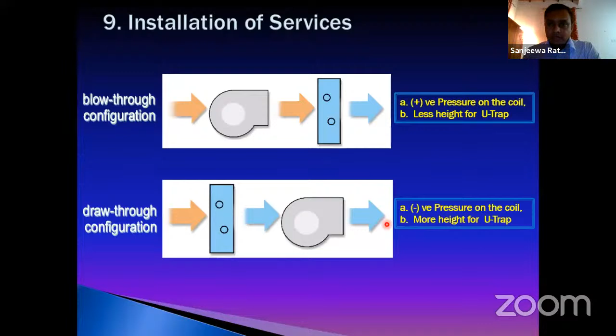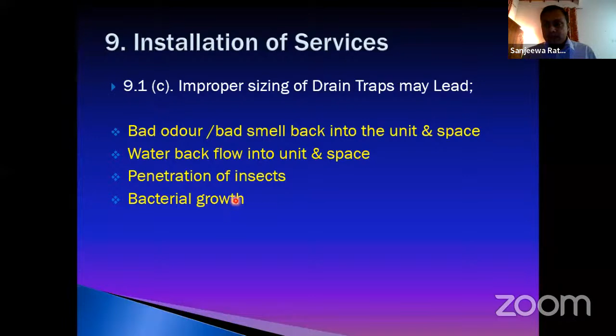Then improper sizing of drain traps may lead to bad odor in the space, water backflow into the space through these drain pans, and penetration of insects can happen. They can come through these drain lines, and bacterial growth can also happen, which is a very crucial thing in hospital areas.